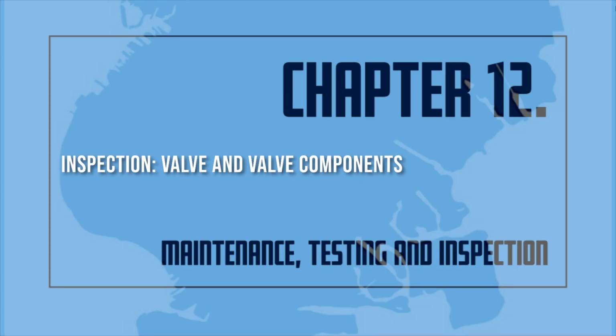The interior of the dry pipe valve shall be inspected annually when the trip test is conducted. Strainers, filters, restricted orifices, and diaphragm chambers shall be inspected internally every 5 years unless tests indicate a greater frequency is necessary. Backflow prevention assemblies. The double and single check assembly valves and double check detector assembly valves shall be inspected weekly to ensure that the OS&Y isolation valves are in the normal open position. Valves secured with locks or electrically supervised shall be inspected monthly.